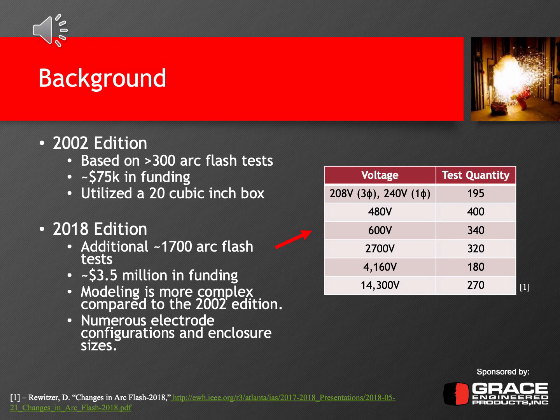One thing to point out is the modeling is much more complex compared to the 2002 edition, and one of the reasons why is that in the 2018 edition, different types of electrode configurations and enclosure sizes were taken into account, along with various voltage levels and various current levels and a number of variabilities in the test. An overview of which tests were performed in the approximately 1,700 tests is shown in the table on the right.